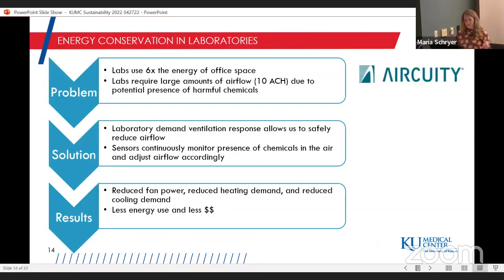The result is we can slow down our fans. We have massive fans that pull air into and out of the building, and we can slow those down. We can reduce how much steam we need for heating and how much chilled water we need for cooling, and the more we do that, the less energy we use. We've seen great results with this project in Hemingway. Unfortunately, our other laboratory buildings don't have that same equipment, so we can't do it there yet, but it's a technology we'd implement in any future lab buildings.